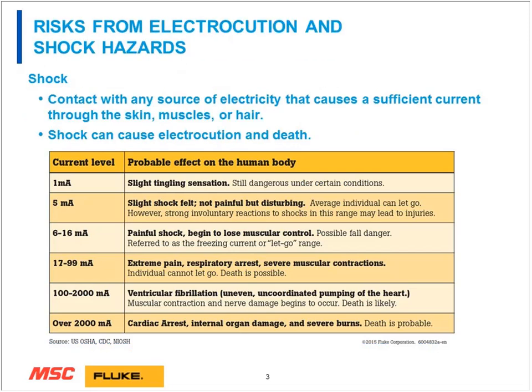In this slide, you can see that there's a variety of different current levels that are applied depending upon the type of shock that you can get. Some, you're just going to feel a slight tingling sensation at about 1 milliamp of current. As the current goes up, you're going to go all the way from the slight shock that you feel to a painful shock where you actually freeze up, and that's called the let-go range. And that is, in fact, between 6 to 16 milliamps, which isn't a lot of current. But that actually locks up your muscles from being able to let go of that probe or that screwdriver or that panel or whatever you're contacting in the way of the active voltage.